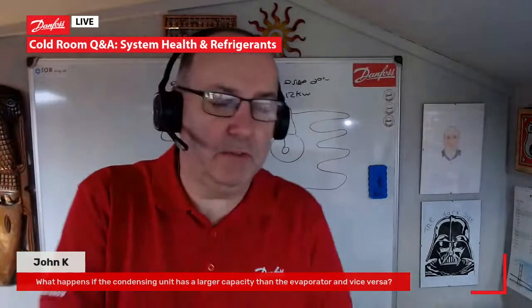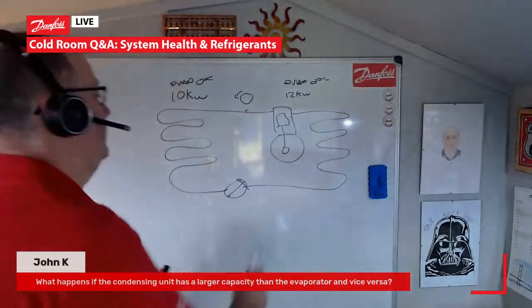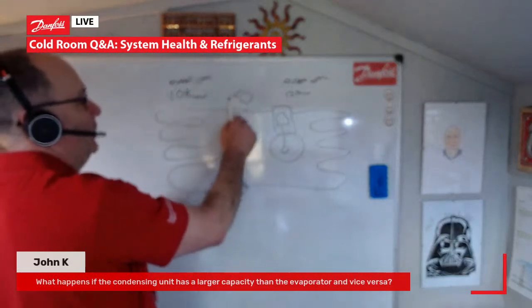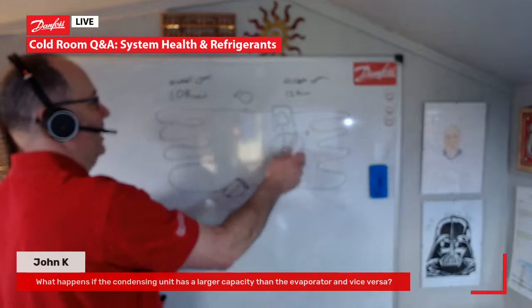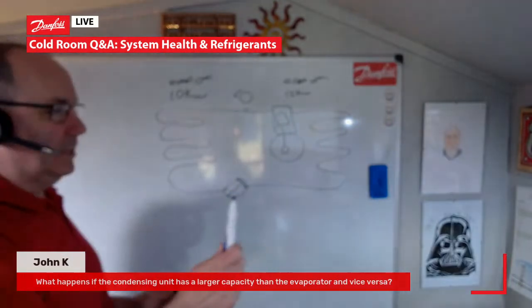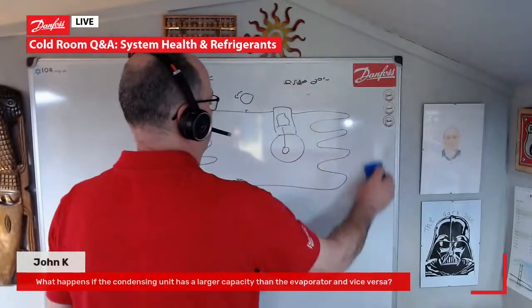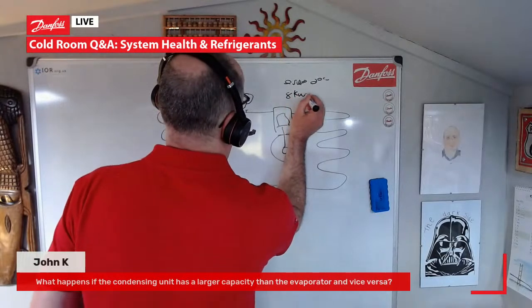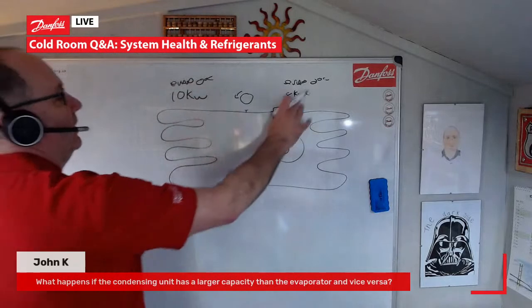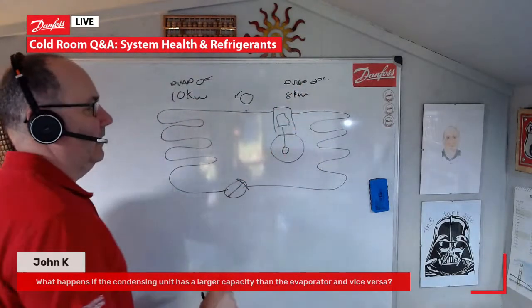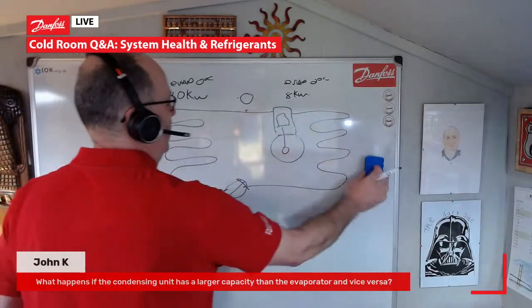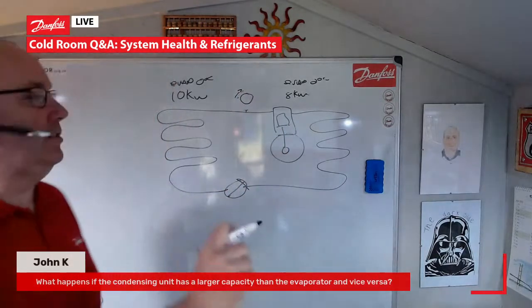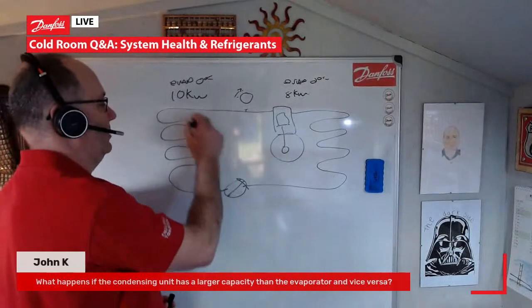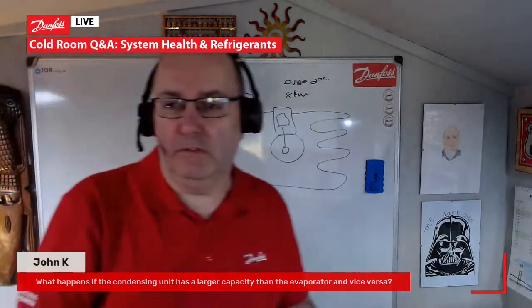You can work this out on balance graphs, balance tables. Most of it's done nowadays, to be fair, on selection software for the evaporators. But in essence, if you've got a larger compressor than the evaporator, your suction pressure will fall a little bit. If you have an evaporator that's larger than the compressor, suction pressure will rise a little bit. Generally, and this is my own personal feeling, I would much rather have an evaporator that is slightly larger than the condensing unit part, because our suction pressure will rise, which is good for energy saving. It's also good because we have a higher relative humidity on our cooler because we're not extracting so much moisture out of the room itself.